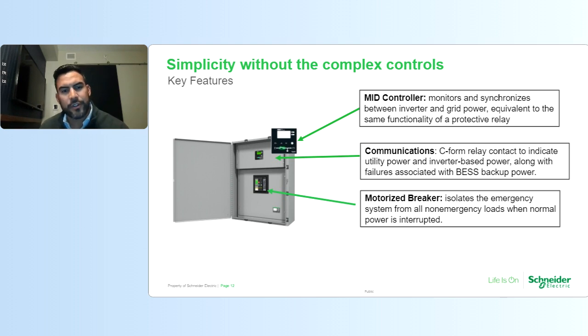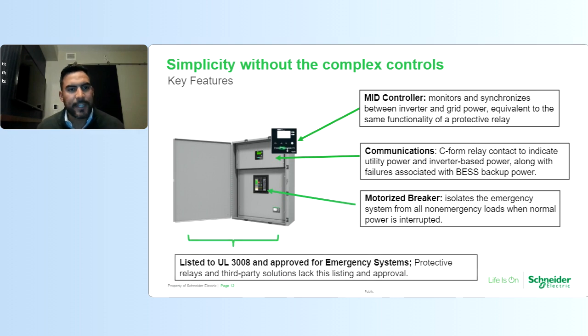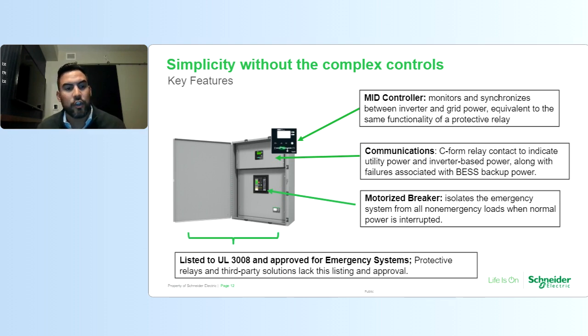We're going to go through the National Electric Code and highlight why this is important. But as you design your microgrid systems, you want to ensure that when you use your energy storage system for backup power, you have those essential or emergency loads separated from your main switchboard, so you're not providing power to the entire system. And all this is linked back to the UL 3008 listing, and is approved for emergency systems. So the code requires that if you use an energy storage system for an emergency system application, you need a UL listed product specifically intended for this application, an automatic interconnection switch to disconnect from the grid and enable that battery energy storage system for backup power.